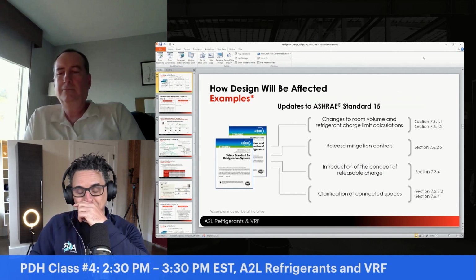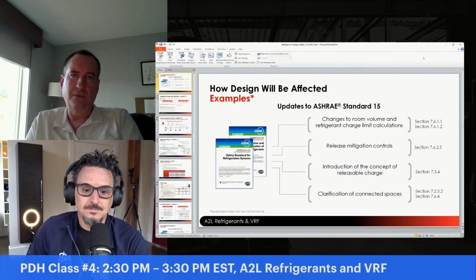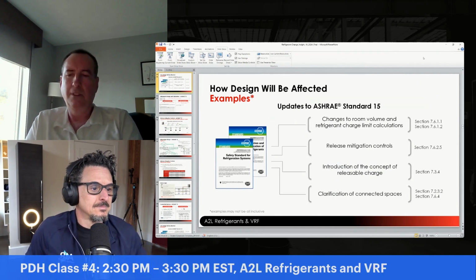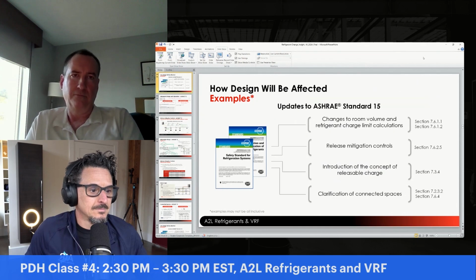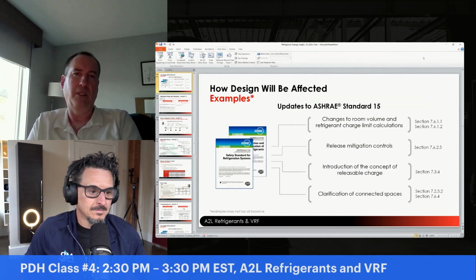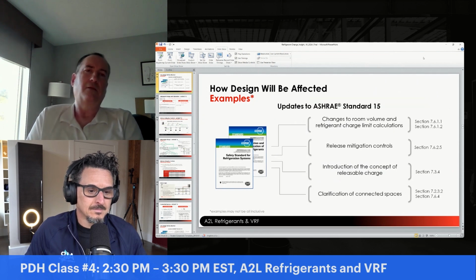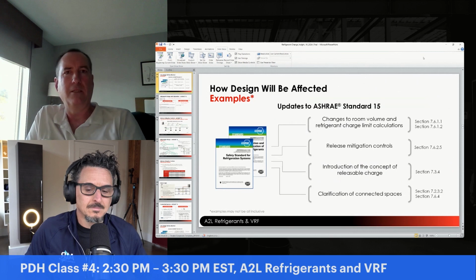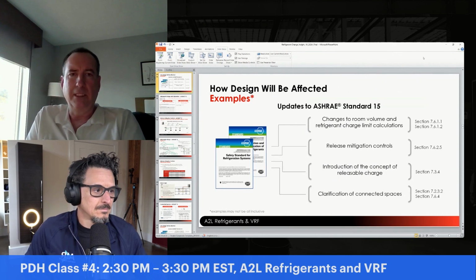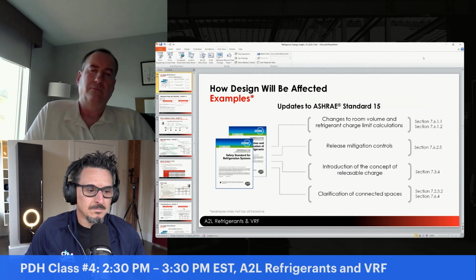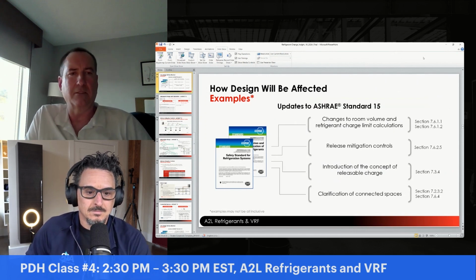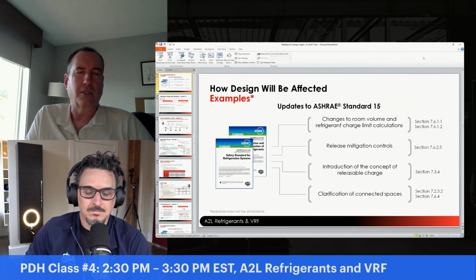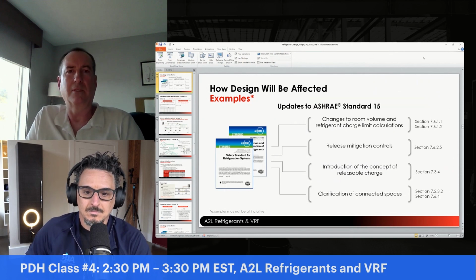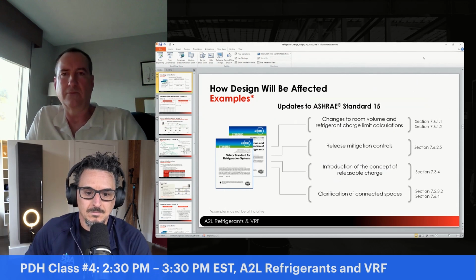So please don't. These updates to ASHRAE 15 2022 include major changes to the room volume and your RCL, or refrigerant charge limit, calculations. It also introduces new concepts of release mitigation controls and releasable charge, and I'm going to get into more detail about all of these. They also clarified some things around connected spaces. Here I've got the sections of the code if anyone wants to look these up - this is where they're all located in the code, in these different sections.